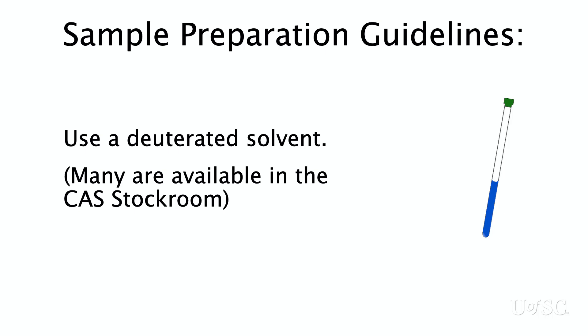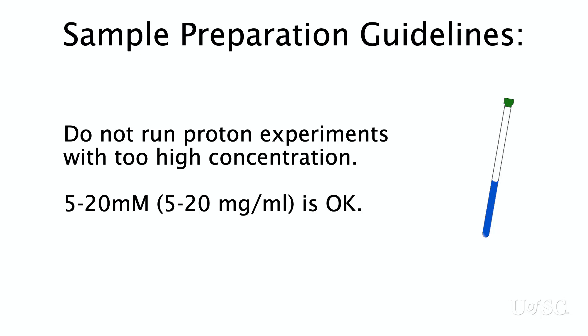See us if you have samples that cannot be run in deuterated solvents. Samples with too high concentration will have problems running. 5-20mg should be enough to get a good proton spectrum with the default parameters.